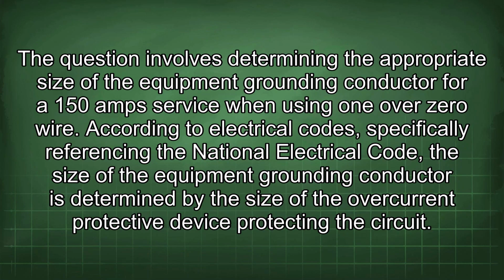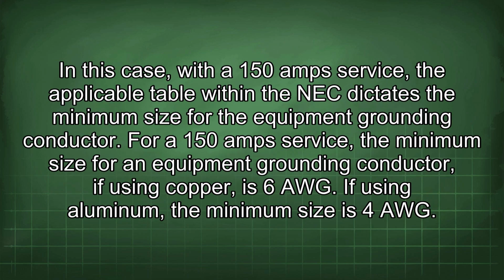The question involves determining the appropriate size of the equipment grounding conductor for a 150 amp service when using 1/0 wire. According to electrical codes, specifically the National Electrical Code, the size of the equipment grounding conductor is determined by the size of the overcurrent protective device protecting the circuit. In this case, with the 150 amp service, the applicable table within the NEC dictates the minimum size for the equipment grounding conductor. For a 150 amp service, the minimum size for an equipment grounding conductor, if using copper, is 6 AWG. If using aluminum, the minimum size is 4 AWG.